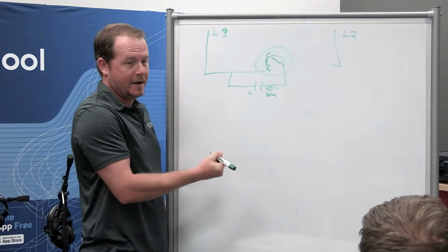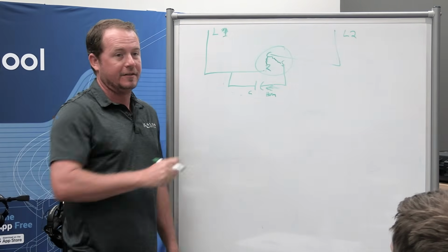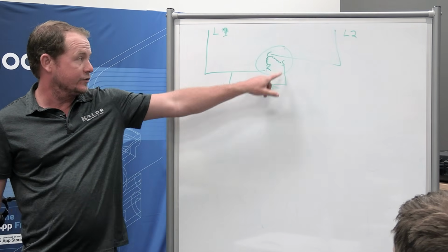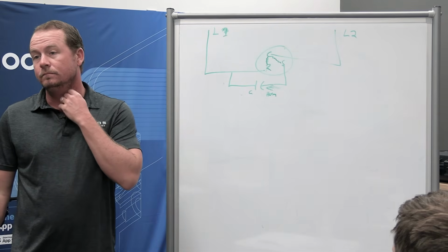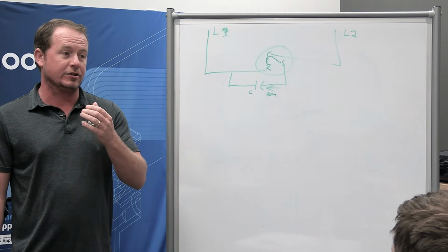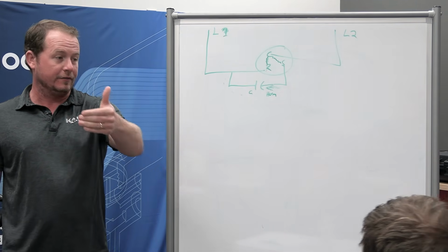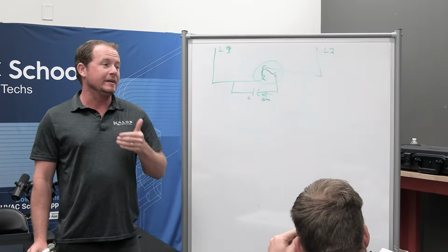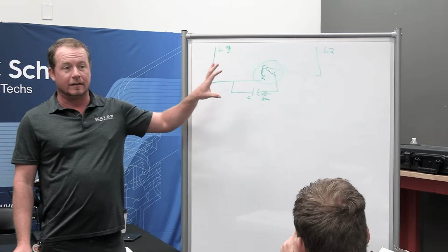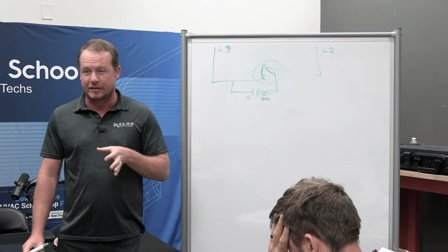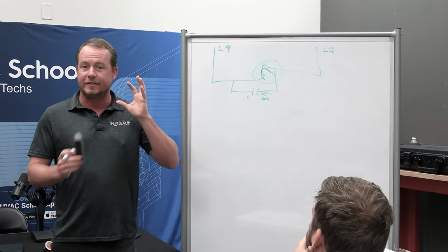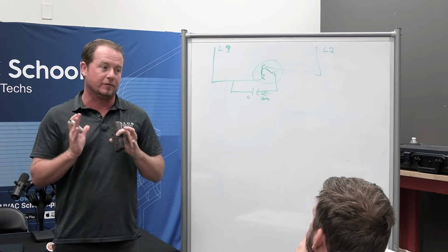It pushes into the capacitor, and then it pushes back out the same way that it came. So when this connects to Herm, the start terminal on the compressor, it's actually going in and out of the start terminal the same way that it came in. Now the reason that it stores electricity in the capacitor, this is kind of like strange magic, but it's actually an attractive force between the two plates because we just have so much surface area.